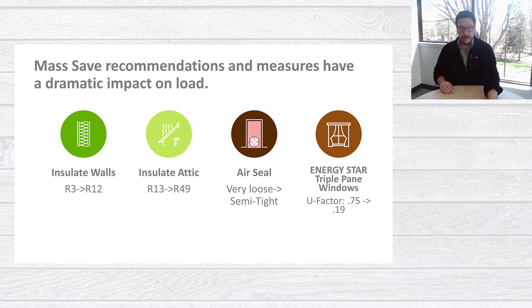When all of those measures became implemented in this home, instead of needing 108,000 BTUs per hour, the load of the home dropped all the way down to 47,450 BTUs per hour. And if I were to be looking at heat pump equipment, I could find that there is a multi-zone heat pump from a major manufacturer. It's 1 outdoor unit. It can support up to 8 indoor units. It has a max capacity of 54,000 BTUs per hour.